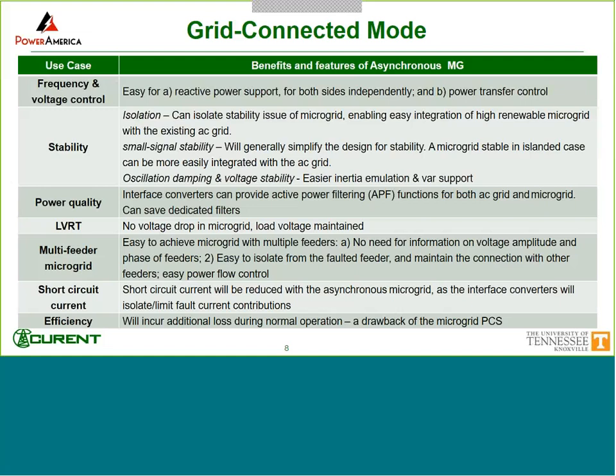It's something I want to explain a little bit, because when you design the microgrid today, if you want to change something, like add some additional PV into it, you would have to redesign the whole thing. But when you have this decoupled link, then that design can be confined to the microgrid itself. Also, for small signal stability, it can simplify the design, like I mentioned, and it can also provide oscillation damping and voltage stability. And for power quality, this interface PCS converter can provide filtering, which will be explained a little bit later, and that will help save some additional filters you may need in the case of nonlinear loads. And low voltage ride-through, I already showed.